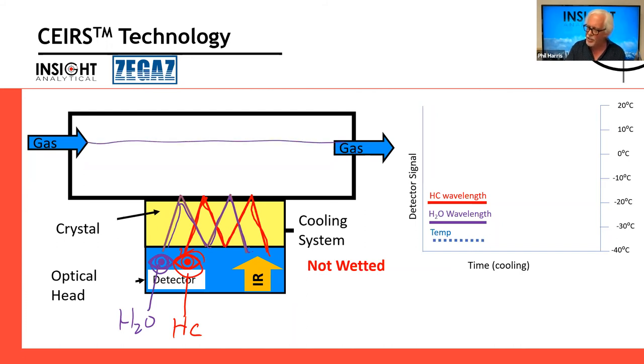We have our natural gas just flowing through the system. Now we start to cool the crystal. So we start out with these two wavelengths of light, two signals at the detector, and we start to cool the crystal down. This trace right here, the dotted trace, is showing the temperatures. As the crystal cools and the gas is flowing by, initially nothing condenses on the surface because the crystal is warmer than both the water and the hydrocarbon dew point. As the crystal gets cooler, one of these things might condense.